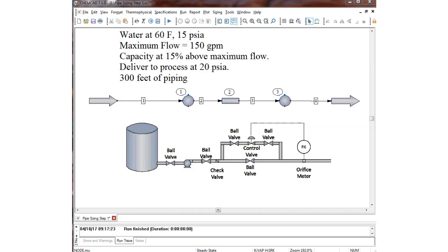We are going to start by looking at the requirements of the process. Imagine we have water in a storage tank where the pressure at the inlet nozzle is 15 PSIA. Our desire is to have 150 gallons per minute at maximum flow, with a 15% cushion above that. Our goal is to deliver water at that flow rate at 20 PSIA, with 300 feet of piping from the storage tank to the process.